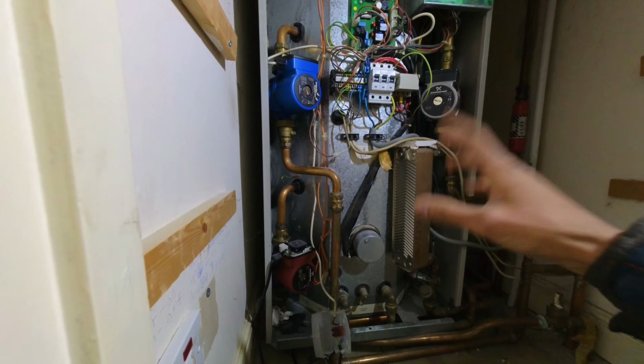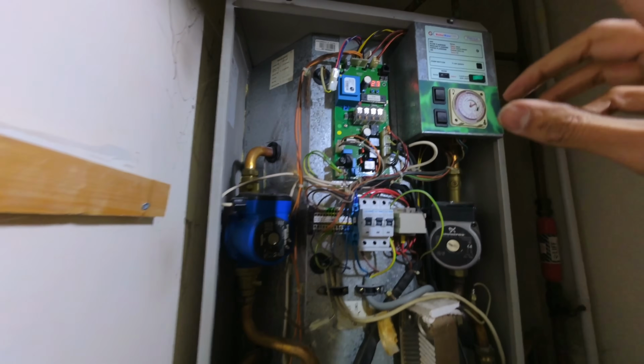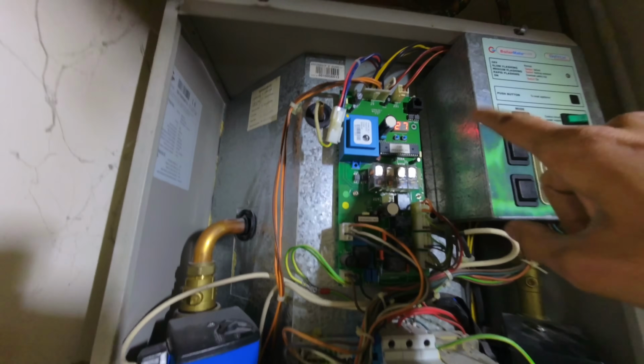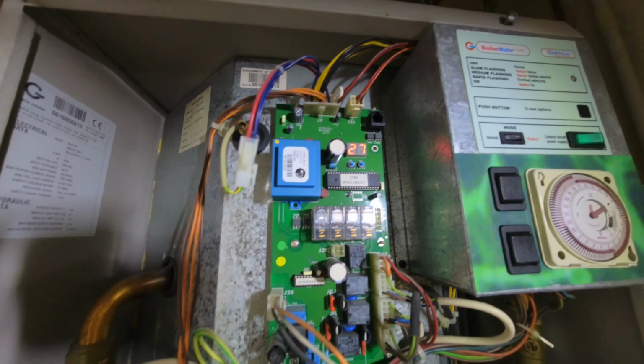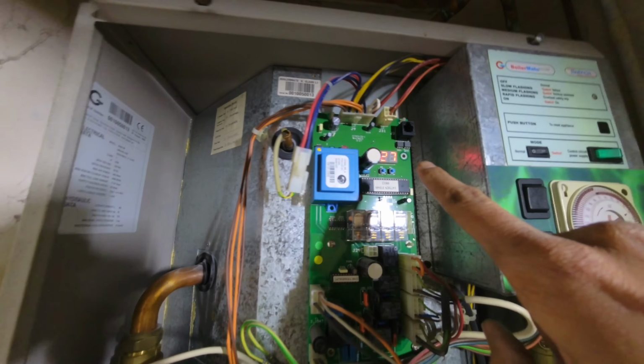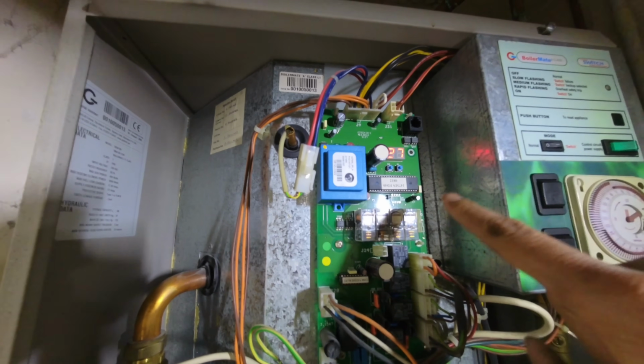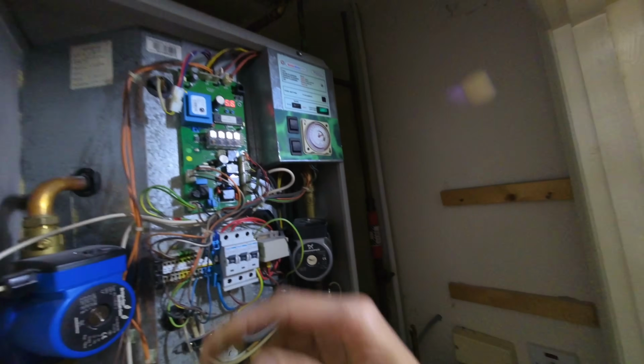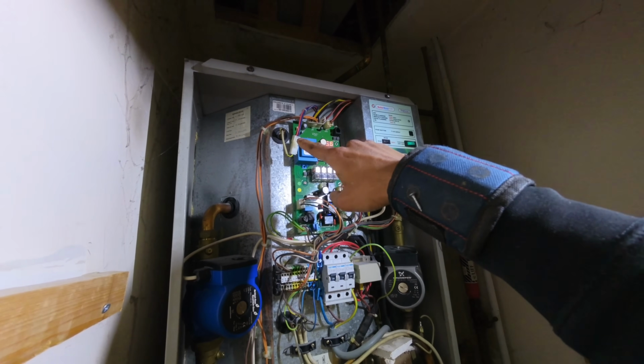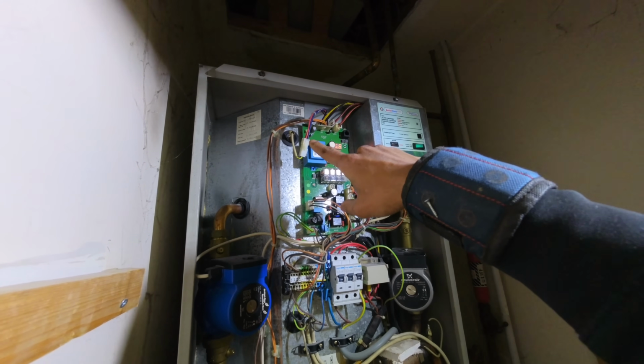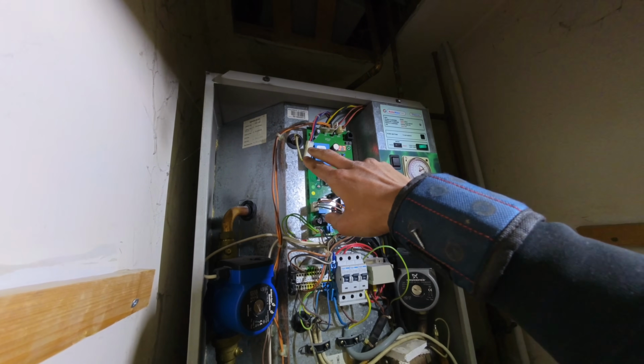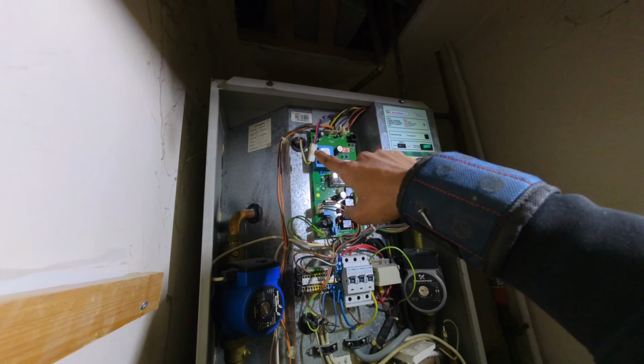Okay, getting somewhere with this - I've spoken to Gledhill, and this control board tells you everything you need to know. Every time it's flashing, it's giving you a sensor reading. So we've got S1 through S6 - six sensors. Two sensors at the top are your overheat stats, and they should be within about a degree of each other - we've got 26 and 27 degrees between S1 and S2.